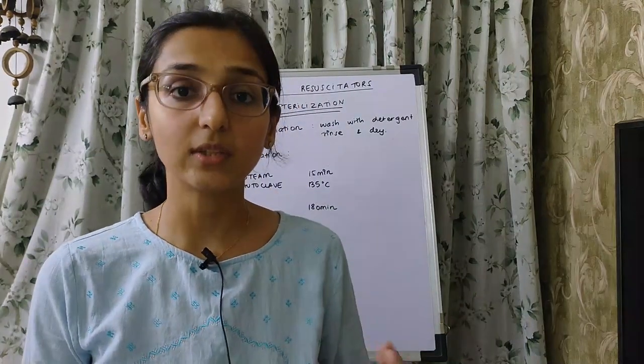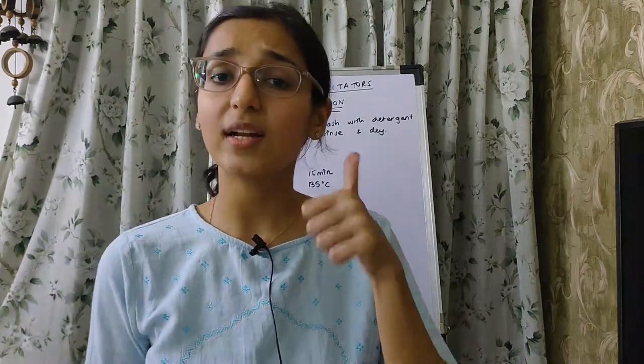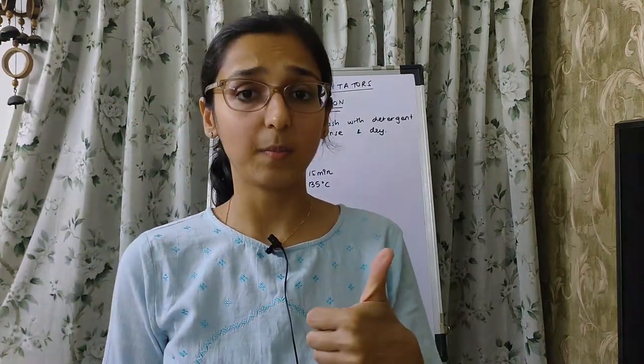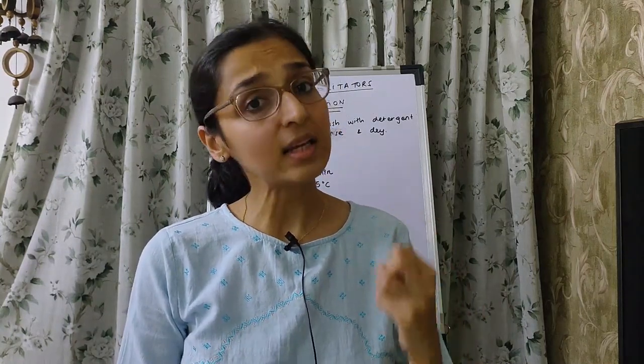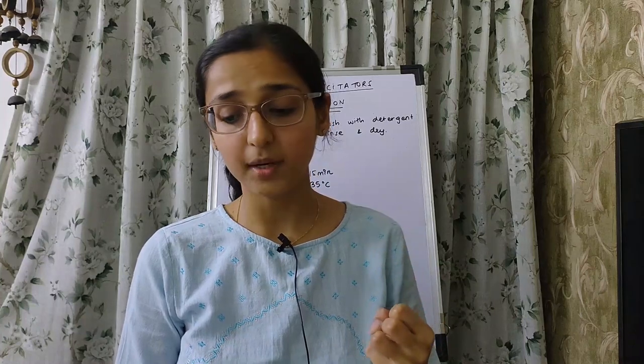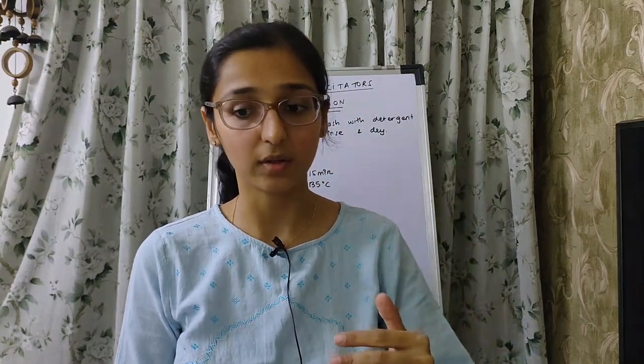Problems that can occur with a manual resuscitator include high peak airway pressures, inadvertent hypoventilation or hyperventilation, rebreathing, low FiO₂ delivery to the patient, and air-trapping.